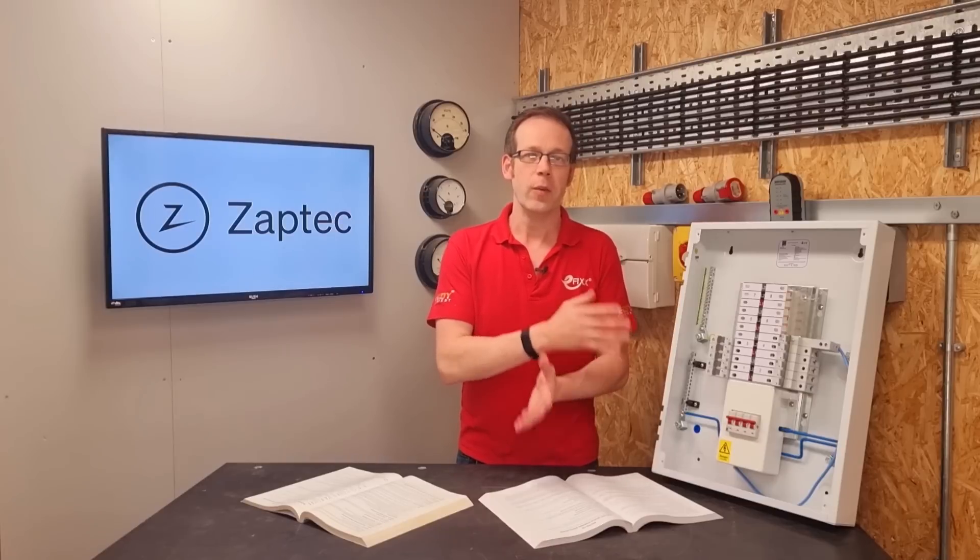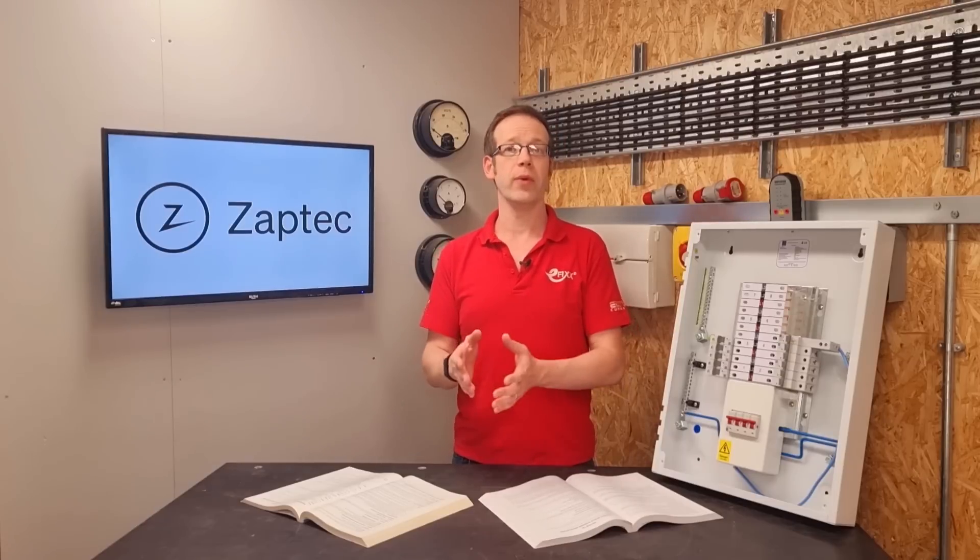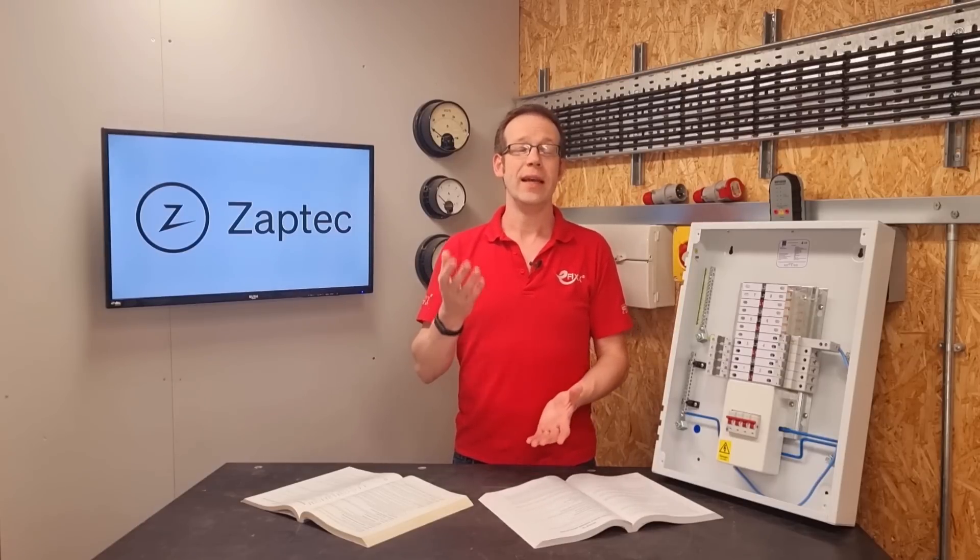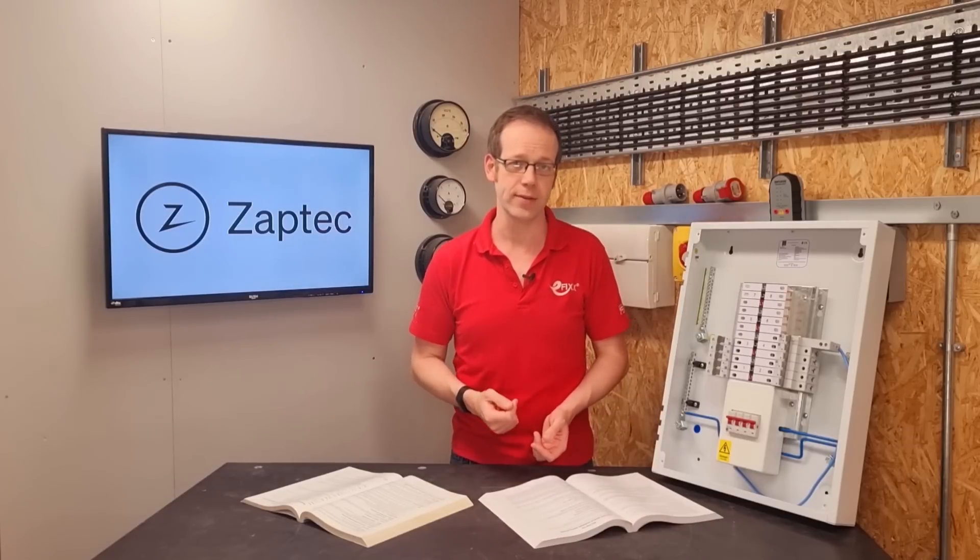When this happens some current will flow down the neutral and the voltage between the bodywork of the car and the earth will rise, and if it rises above 70 volts then anyone touching the car could be in serious danger if a PEN fault then occurs.